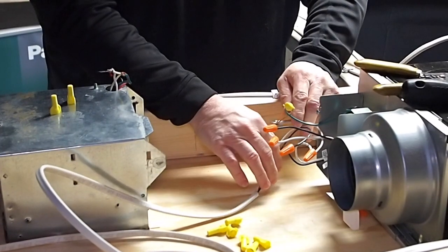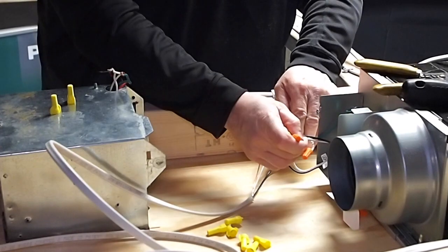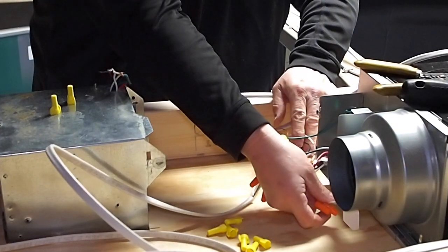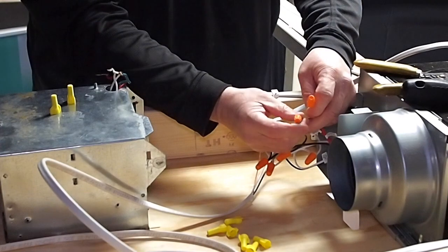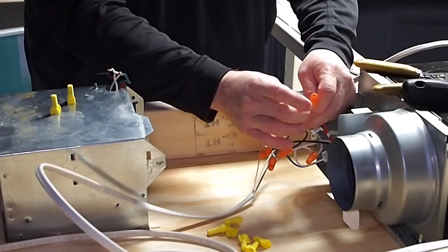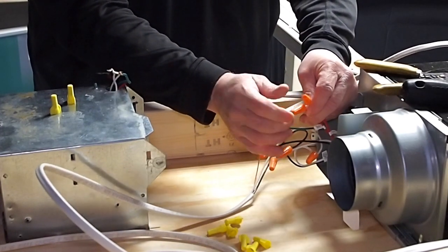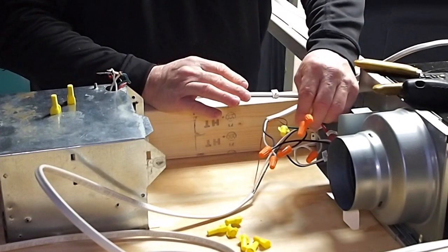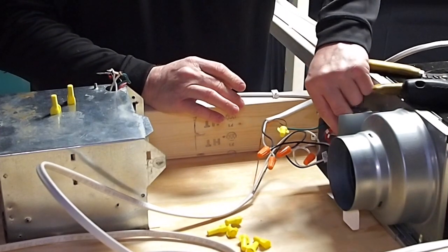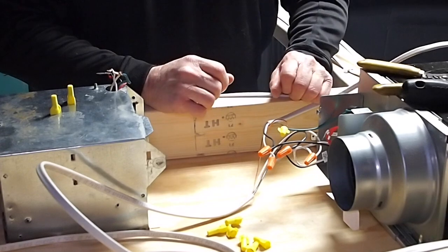Now we have switched power to the light. We have constant power to the fan. We have the red signal wires here, which have already capped those off individually. You don't want to put those together. We are not going to use them in this scenario. You are just going to get capped off and tucked back in the fan in case later on somebody wants to use those.